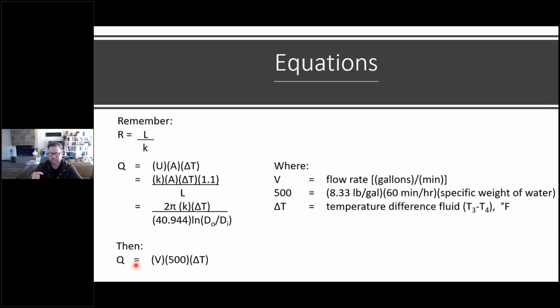But in this case, it's not necessarily doing that. So we have to recognize some of the limitations here. But that is the next equation. I think this one is one that most of us are familiar with, which is our volumetric flow rate times a 500 constant, assuming imperial US units, like gallons per minute and Fahrenheit, times our temperature differential of our fluid. So again, one is the conductivity through the insulation, the other one is the fluid temperature differential.